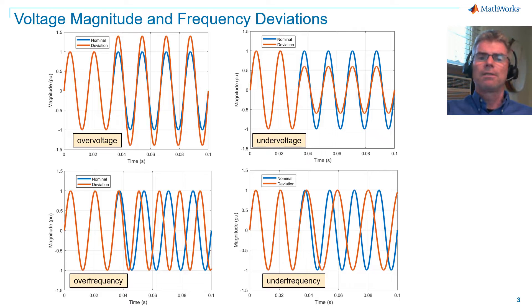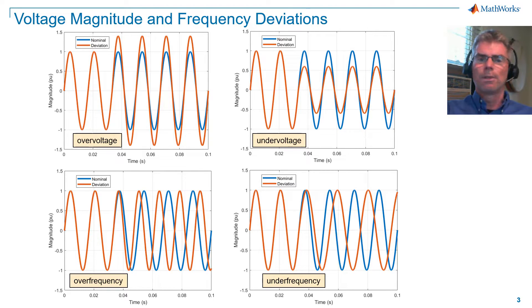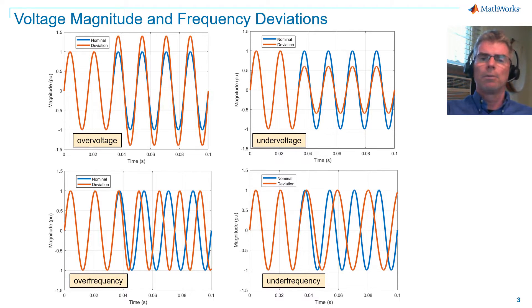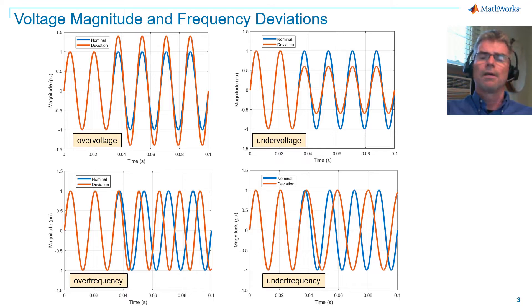Here I'm showing some fundamental deviations in voltage magnitude and frequency. At the top left, we have an overvoltage, where the voltage magnitude is greater than nominal magnitude for an extended period of time. If the voltage increases in magnitude for a short duration, it's called a voltage swell. On the top right, we have an undervoltage, where the voltage magnitude is less than nominal magnitude for an extended period of time. If the voltage decreases in magnitude for a short duration, it is called a voltage sag.